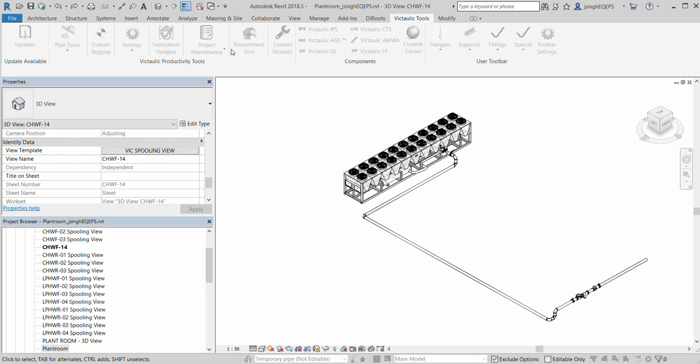Whenever you are doing a cut list, you have to specify to Victaulic what your maximum pipe length is. Here, my supplier can provide a maximum pipe length of 5940 mm, and the minimum is 80 mm. Why 80 mm? This is a very good point. Whenever you have to join two pipes through a coupling, not welding, you need to provide at least 80 mm of pipe segment in order to make the joint. That's why my minimum is 80 mm.